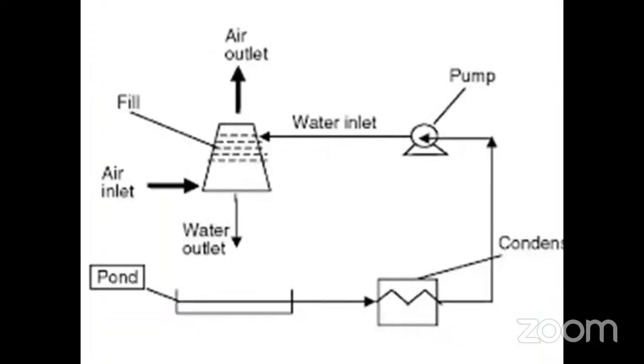Okay, sir. The basic principle is evaporative cooling. That's all. So in one word we can say evaporative cooling. The minimum temperature we can reduce the hot water to is the wet bulb temperature. Beyond which we cannot reduce the temperature, even theoretically. This is the working principle.